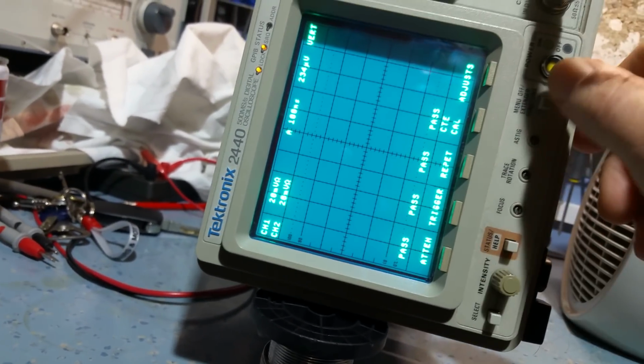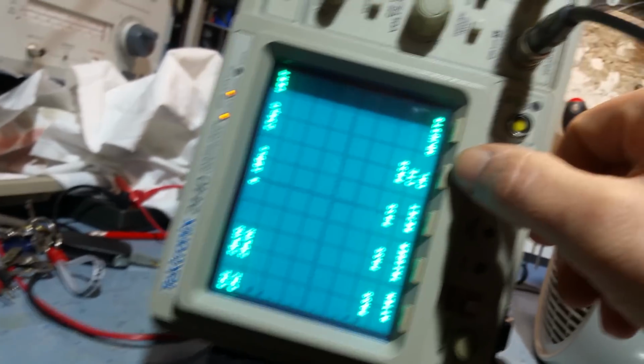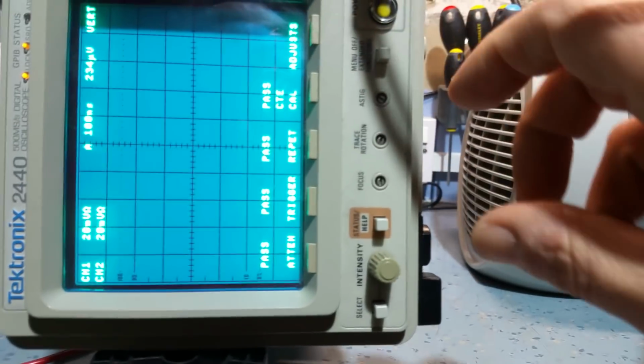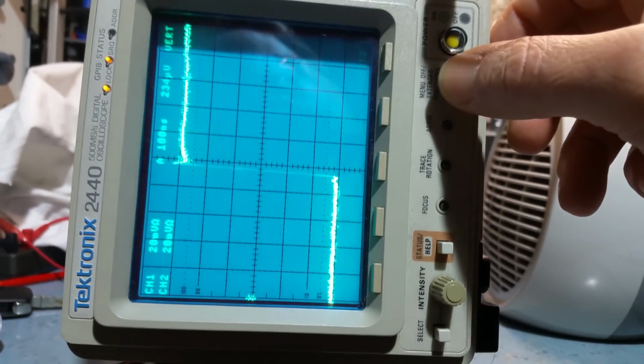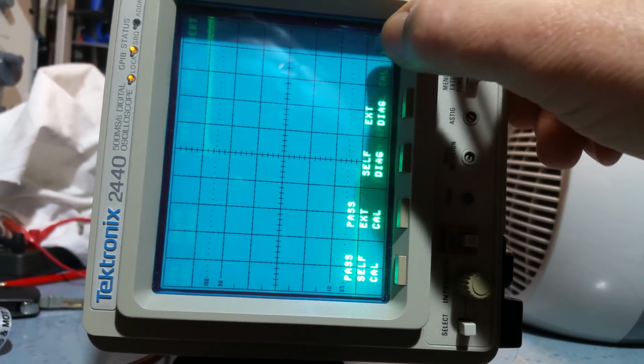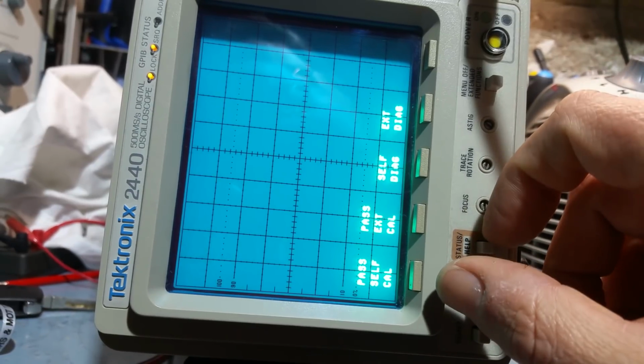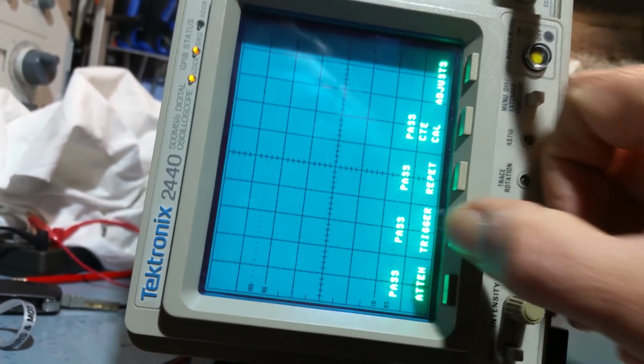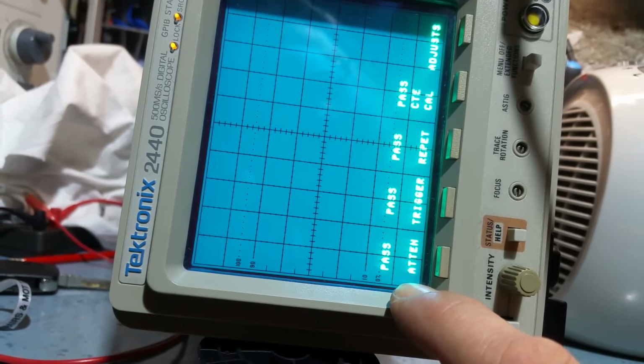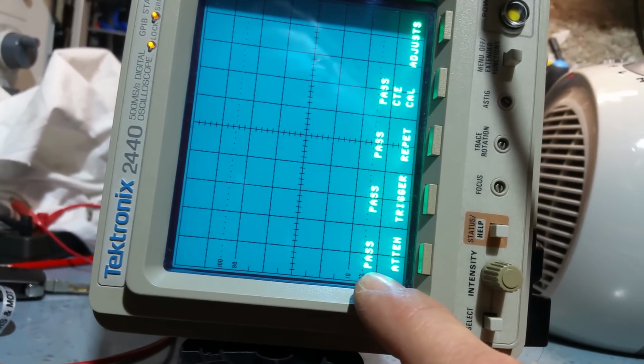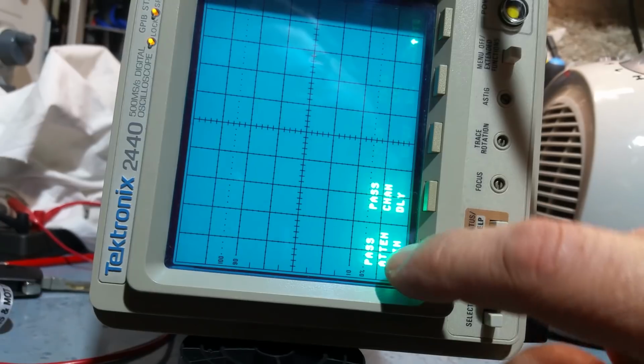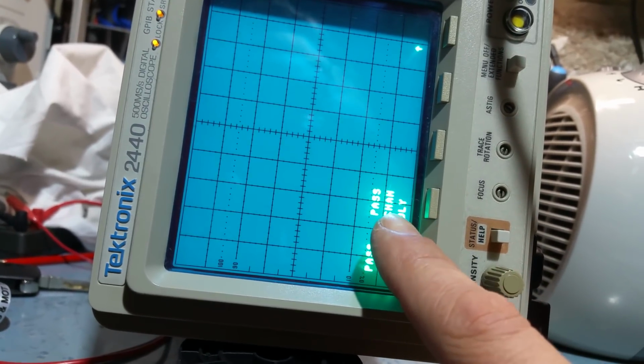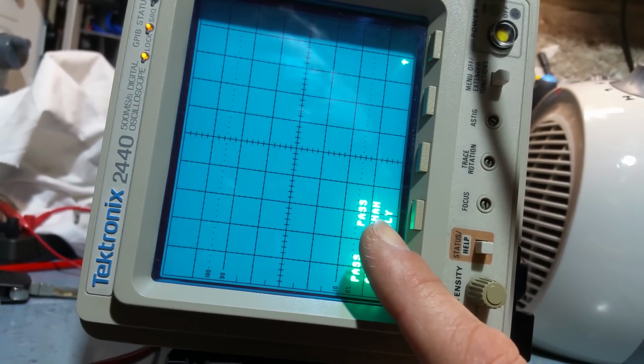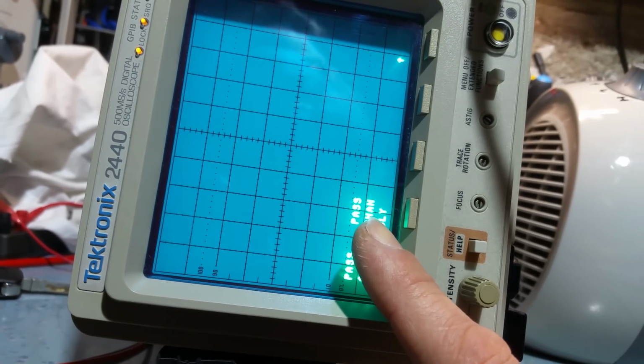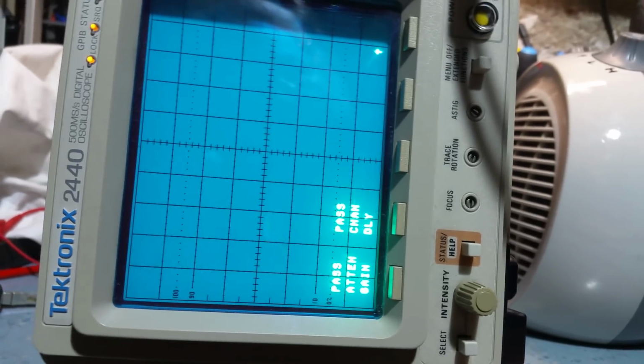There was another test here that was really confusing. Sorry, this is upside down. If I turn the camera around the other way, it will flip it vertically and it will look really weird. So, in the calibration diagnostic settings, there's a number of different external calibrations. This one here is easy enough to do. You do attenuation and it passes. But there's also channel delay here. Basically that looks at the two inputs and makes sure that the phases are matched together. So you put two signals into the input of the scope with a square wave, and it matches those up.